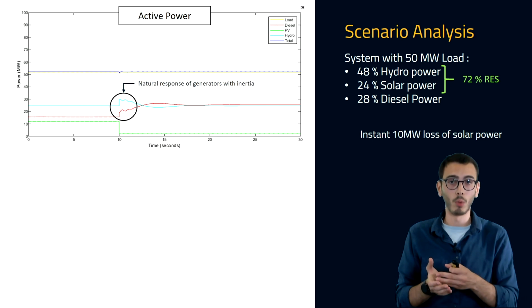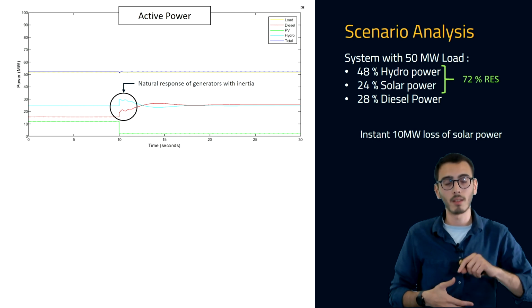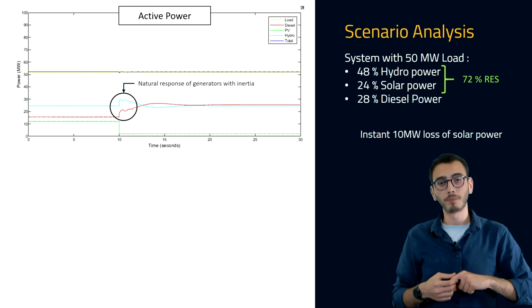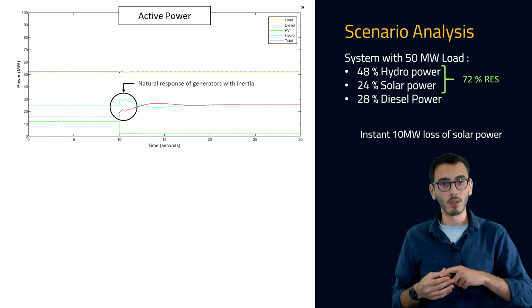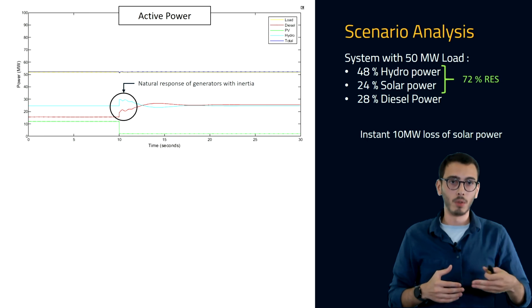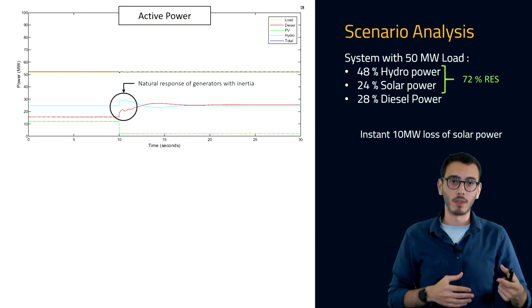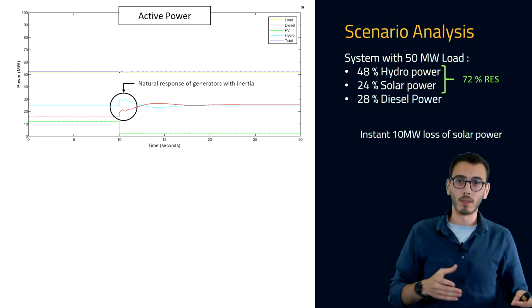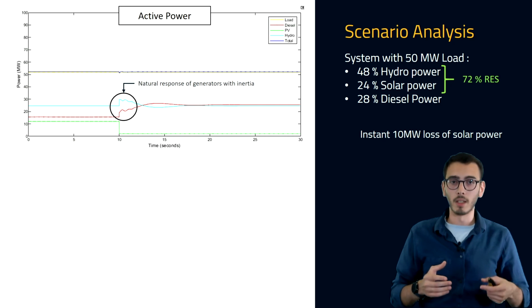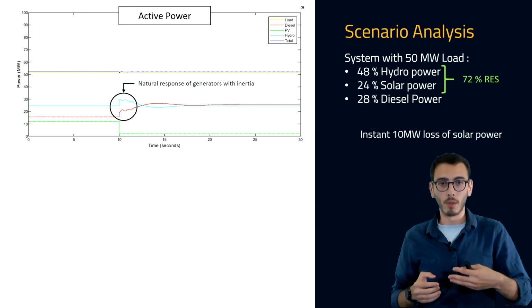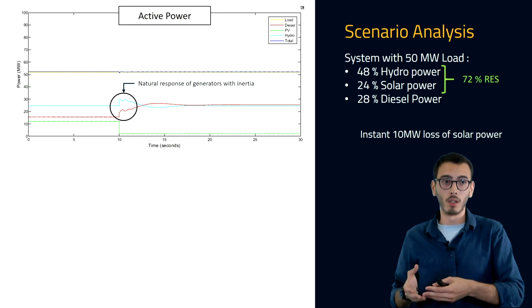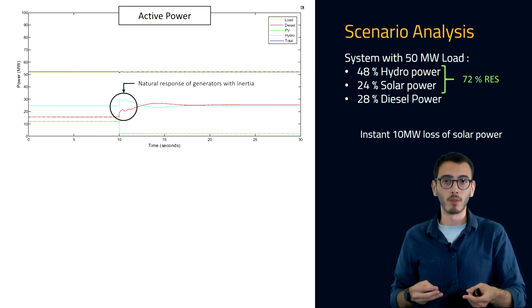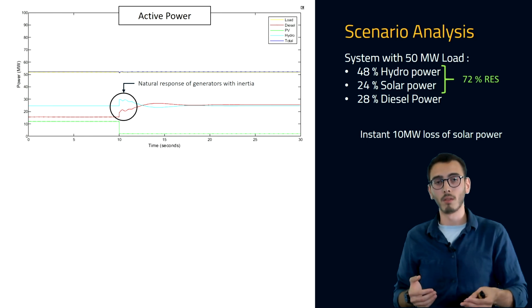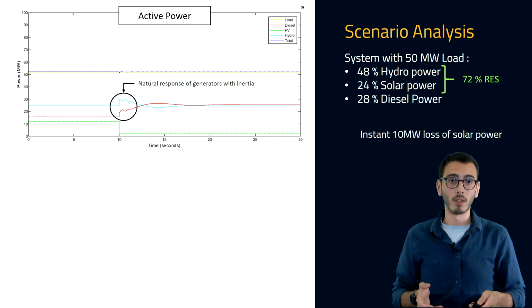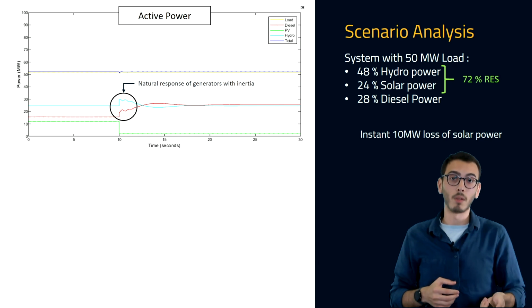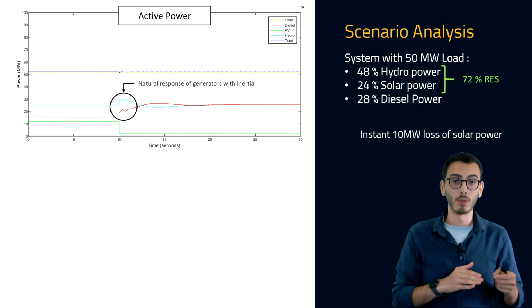And we can see for the blue and the red line that there is an instantaneous augmentation of power that is due to inertia, but this is not sustainable. After 2 or 3 seconds, this power is going to go down again. And if the main producer of electricity, which is the hydro turbine in the case of hydroelectricity, and the diesel generator in terms of the diesel power plant, do not provide this extra power, then the power is going to go back to where it was before.